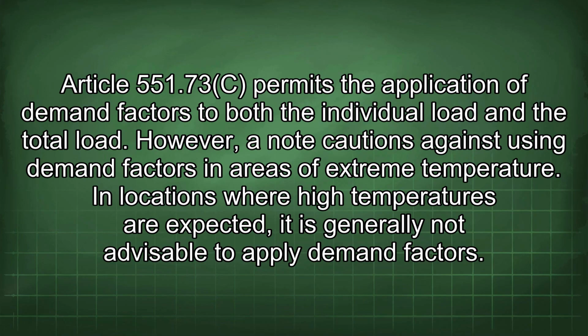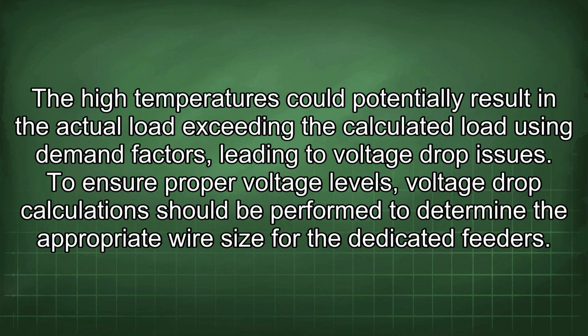551.73c permits the application of demand factors to both the individual load and the total load. However, a note cautions against using demand factors in areas of extreme temperature. In locations where high temperatures are expected, it is generally not advisable to apply demand factors.